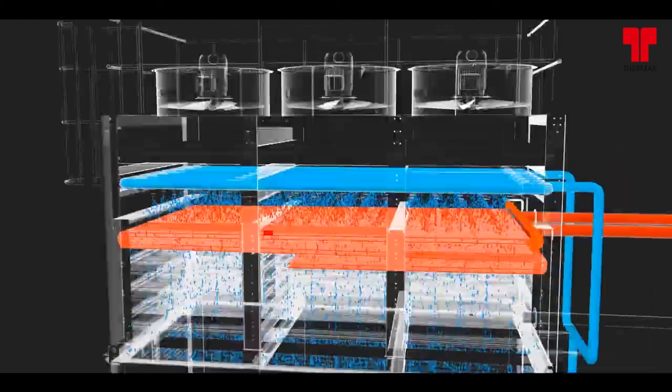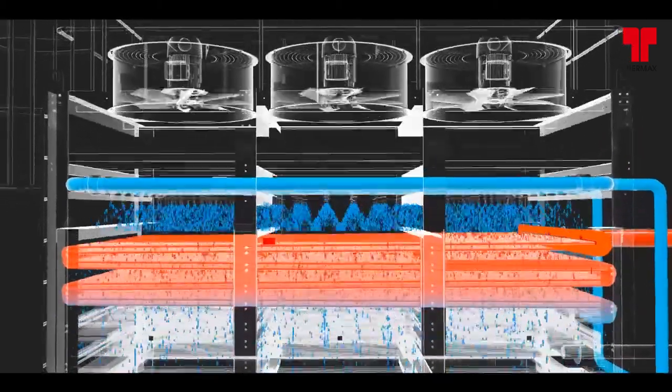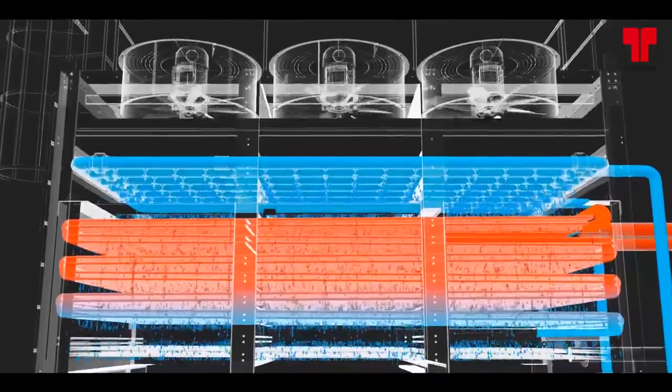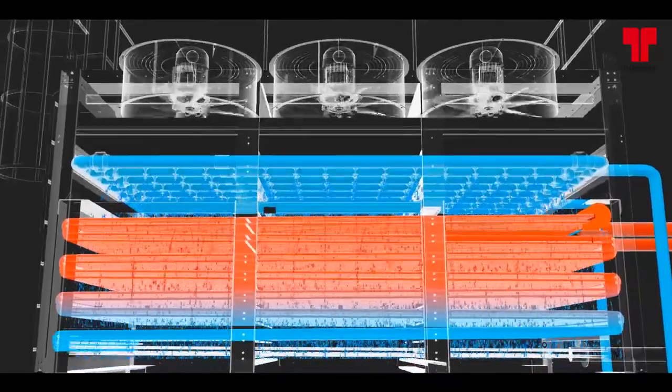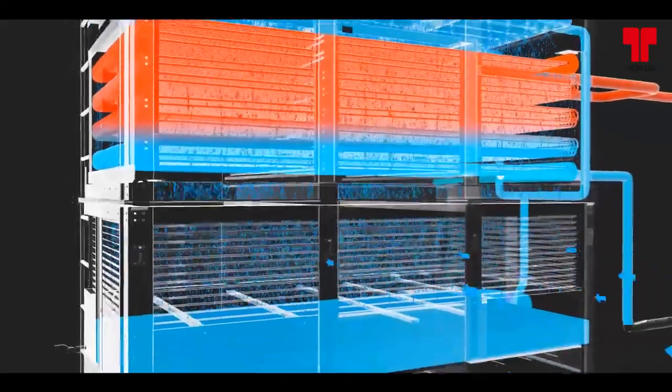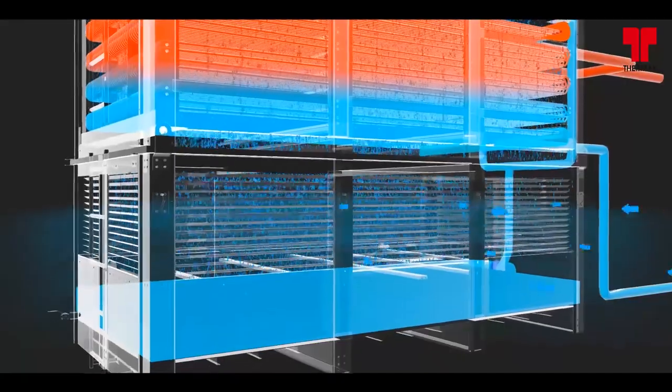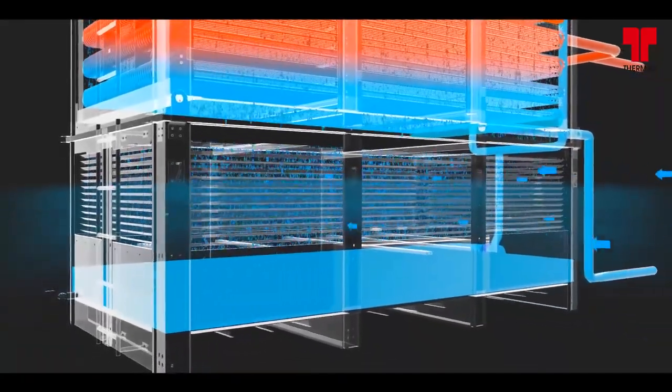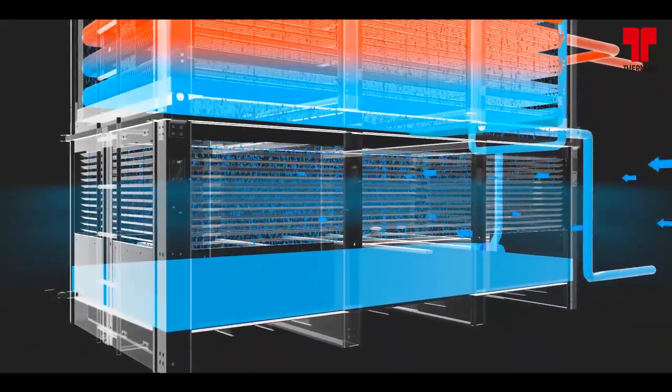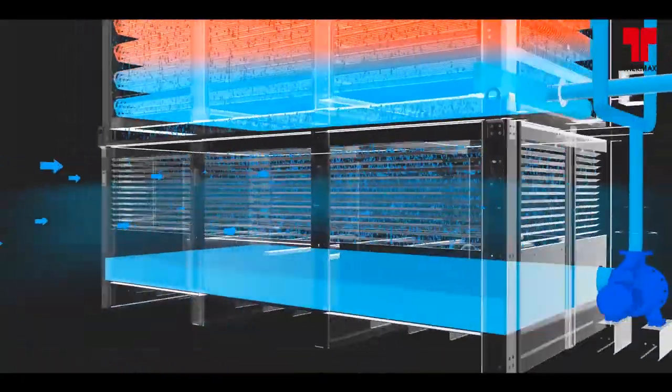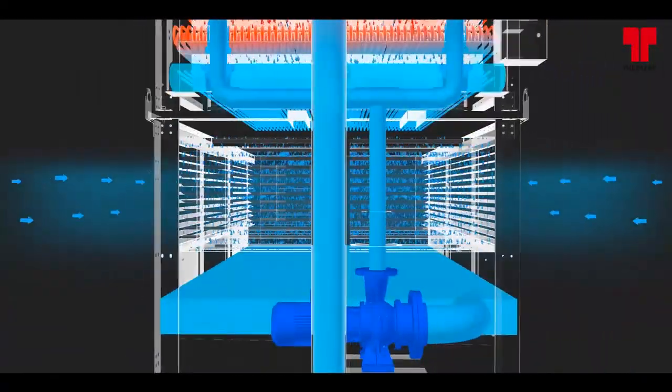This heat is removed by the spray water cascading downward over the tubes. Air drawn in through the air inlet louvers at the base of the condenser travels through the heat exchange coil at a direction opposite to the spray water flow. The water evaporates, removes the heat and cools the spray water.